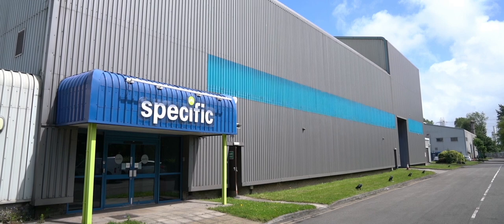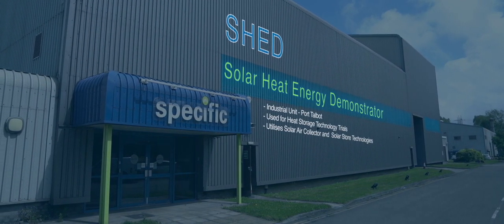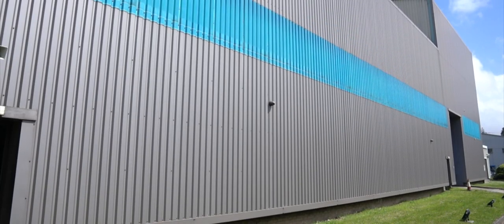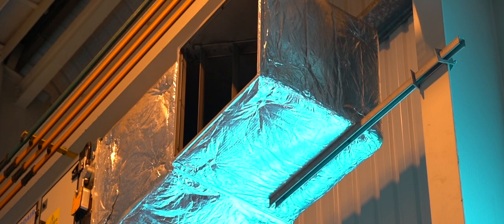The solar heat energy demonstrator building is our biggest retrofit project, on an old industrial unit in Margam, Port Talbot. It's used mainly to trial heat storage technologies. The south-west facing wall and part of the roof of the unit are fitted with Tata Steel's transpired solar collector. A boundary layer of air is heated by the sun and drawn into the building through the tiny perforations in the cladding by a fan.